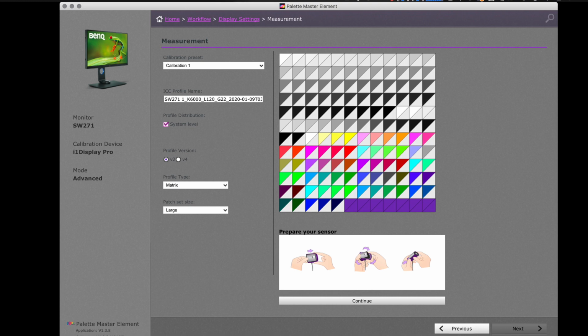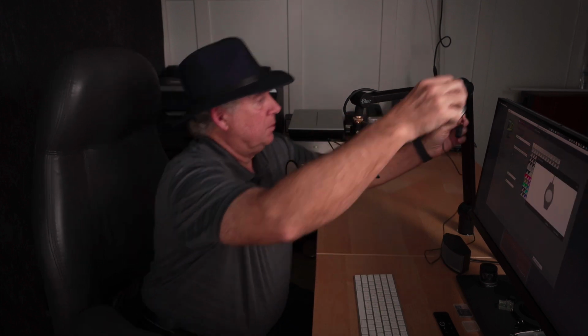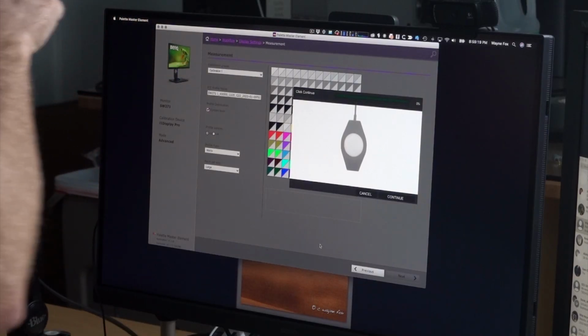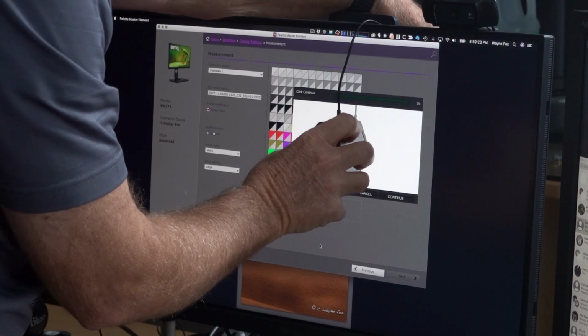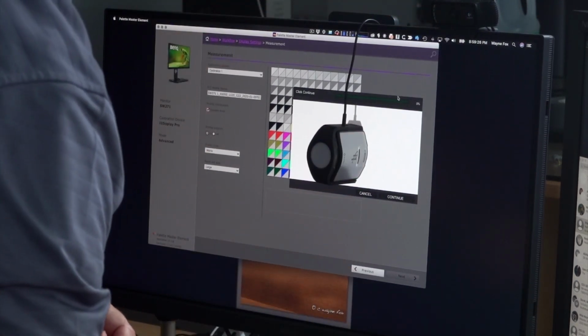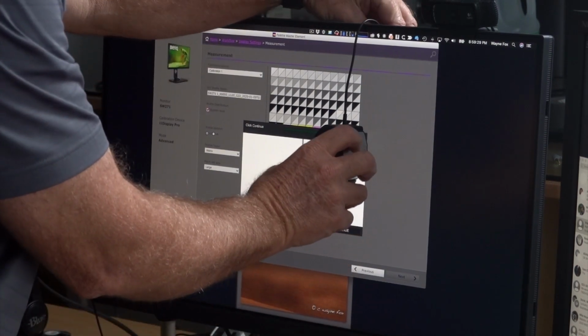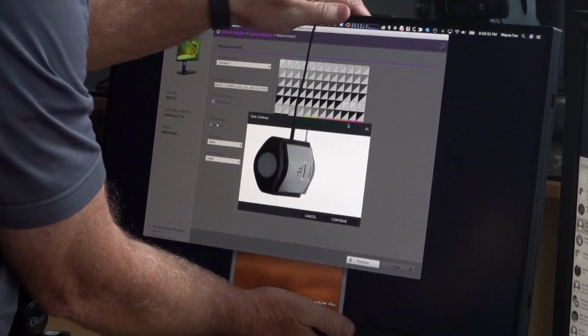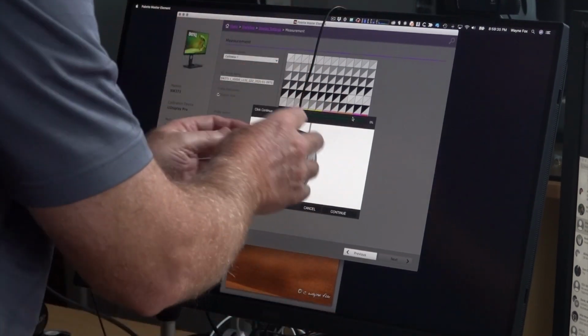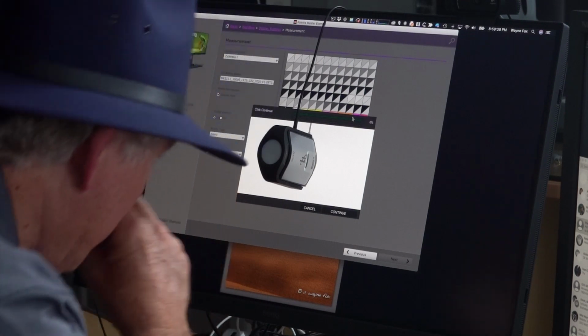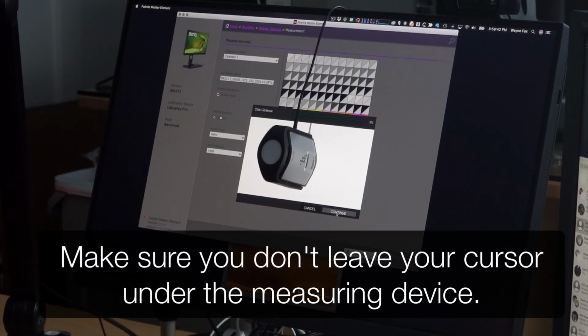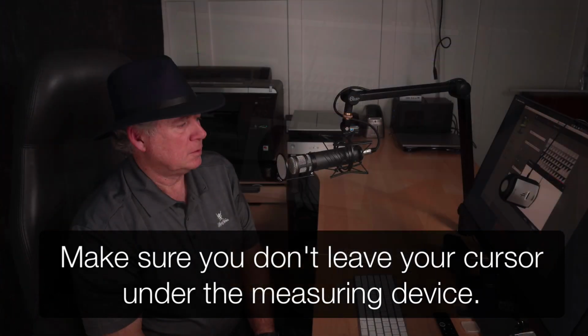It's going to give us all the instructions. So it says to turn the sensor like that. Then we hit continue. Now it tells us to hang the sensor. The best way to hang the sensor, hopefully you can still hear me, is to hang it over the back with the weight, and position it where the little picture is. I usually move the window over to the middle so that the sensor is positioned in the middle of the display. I always tilt the monitor as far as it'll go so gravity will keep it flat against the panel when I do the measurement. And then you hit continue. It will take a little while, and when it's done, I'll be back.